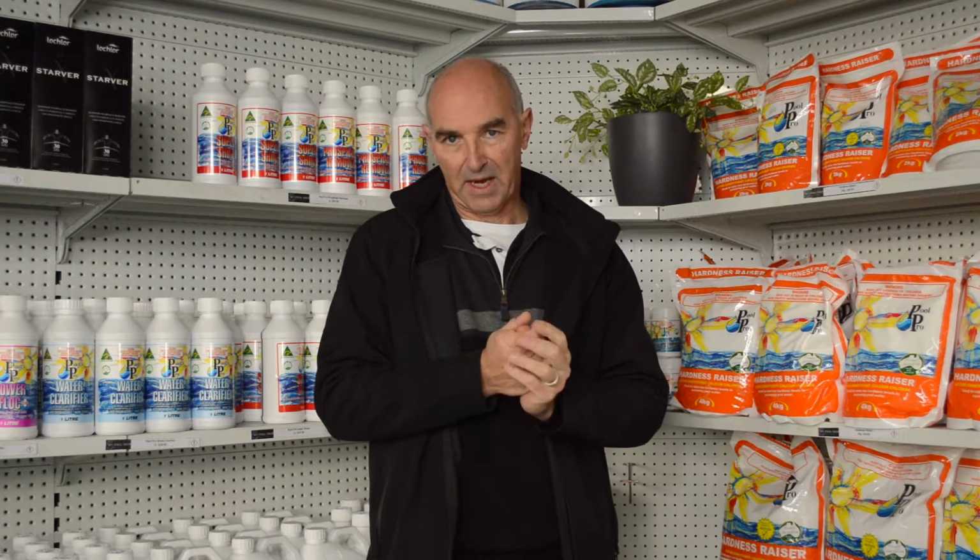What that means is, if the total alkalinity is way too high, when you add some acid to reduce the pH of the water, the pH will initially come down, but it will bounce back up again quite quickly. And conversely, the opposite is true. So therefore, if your alkalinity is too low, if you were to treat the pH, you will find that it will drop like a stone much further than you want it to be. And therefore, your water will become quite corrosive because it is at the acidic end of the pH range. And obviously the opposite is true again. If the alkalinity is way too high, the potential to form scale presents itself.